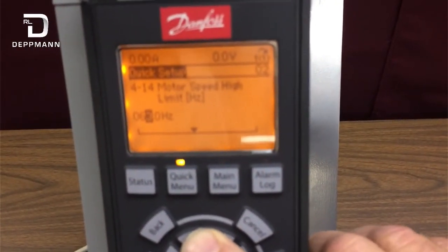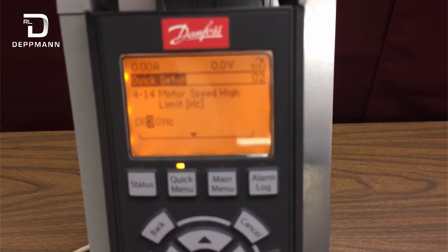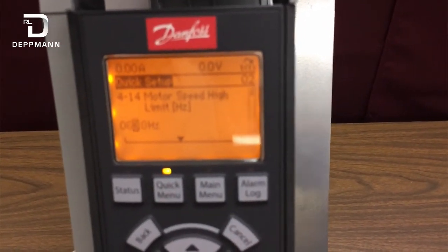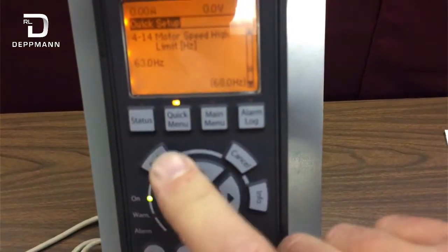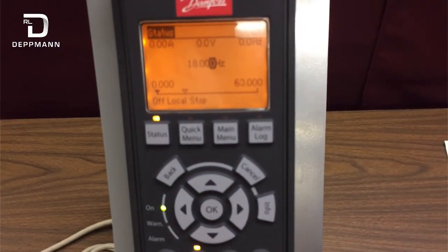So when I push the OK button, that moves the cursor to the last digit. We're going to change that and scroll up to 63, a maximum of 63 Hz. Once I have that set, I'll push the OK button. That accepts the new parameter, and now we can go back until we get to the main screen.